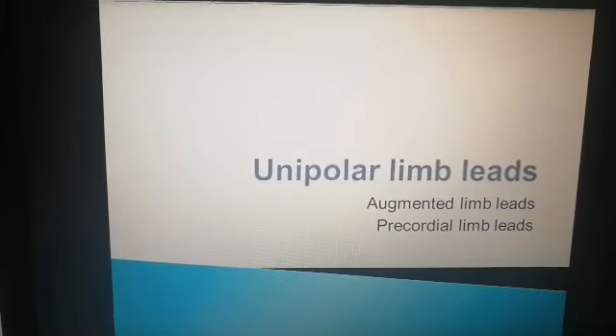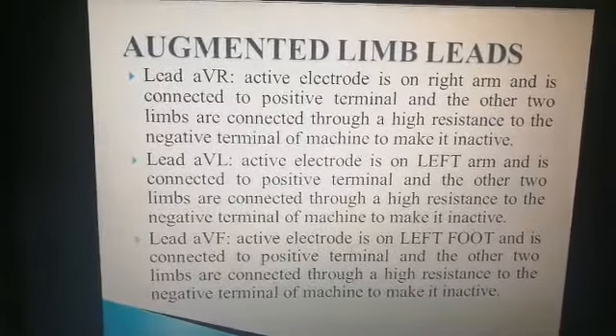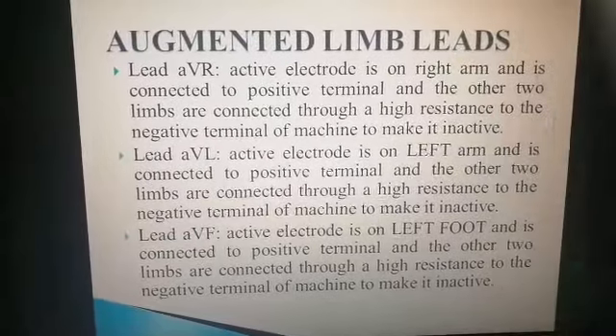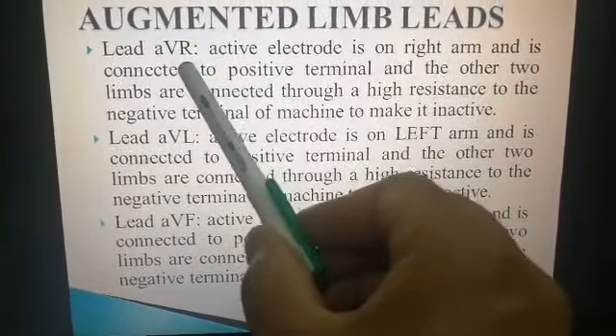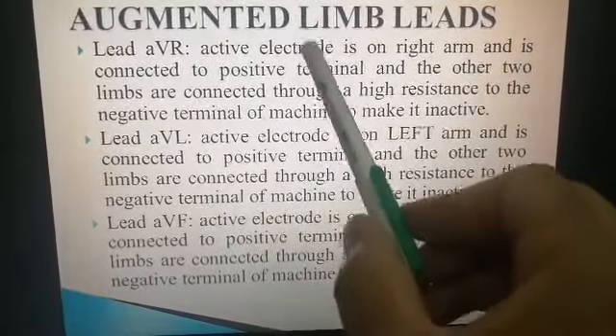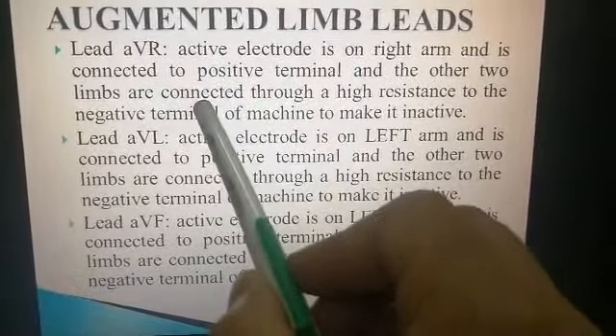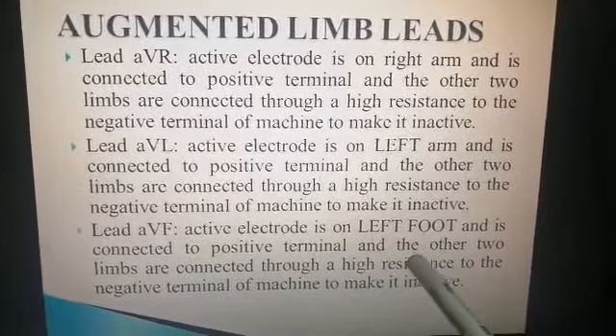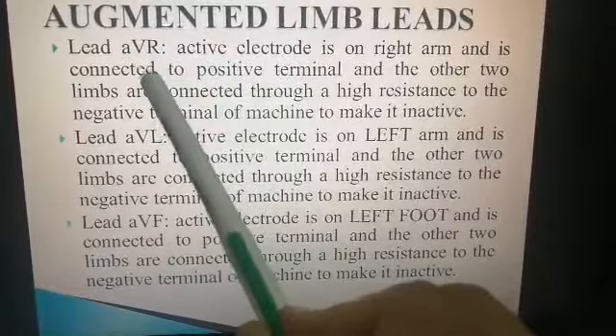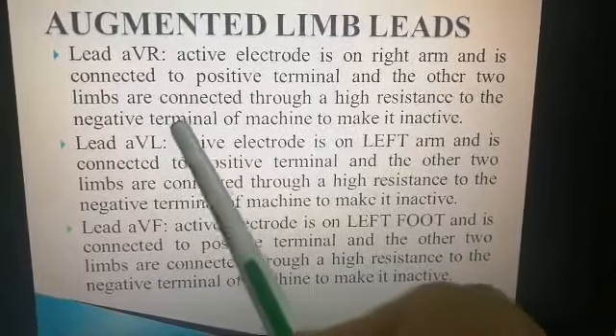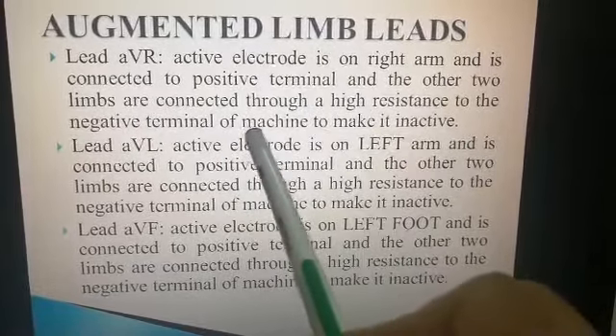The unipolar limb leads are of two types: augmented limb leads and precordial chest leads. In augmented limb leads there are three types: AVR, AVL, and AVF. In AVR, 'R' means right arm — so right arm has the active electrode connected to the positive terminal, while the other two limbs, left arm and left foot, are connected through high resistance to the negative terminal to make them inactive.